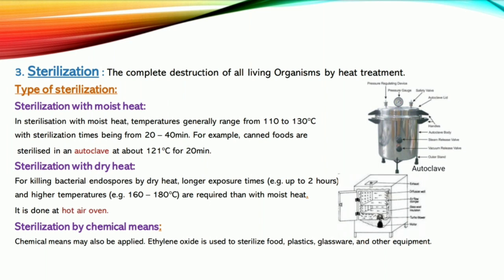Second one is sterilization with dry heat. It is used for killing bacterial endospores by dry heat. Longer exposure times, for example up to 2 hours, and higher temperatures, for example 160 to 180 degrees Celsius, are required as compared with moist heat. Specifically, it is done in a hot air oven. Third one is sterilization by chemical means. Chemicals could also work as a helpful ingredient for it. For example, ethylene oxide is used to sterilize food and also plastics, glassware, etc.